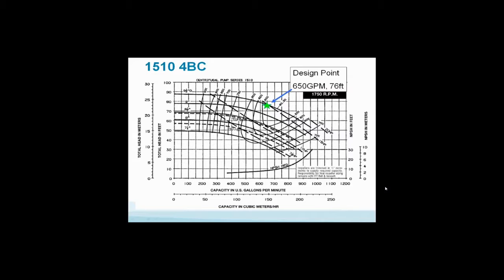The green star is where it's been designed by the engineer: 650 GPM, 76 feet of head. Where are we? About 83% efficiency, midpoint. Beautiful selection of a pump. Great selection of a pump. Will the system run there? Let's turn the pump on and see what happens.